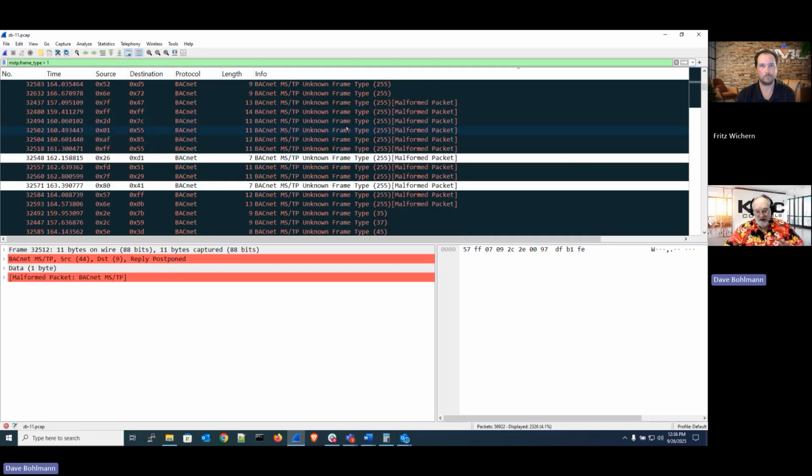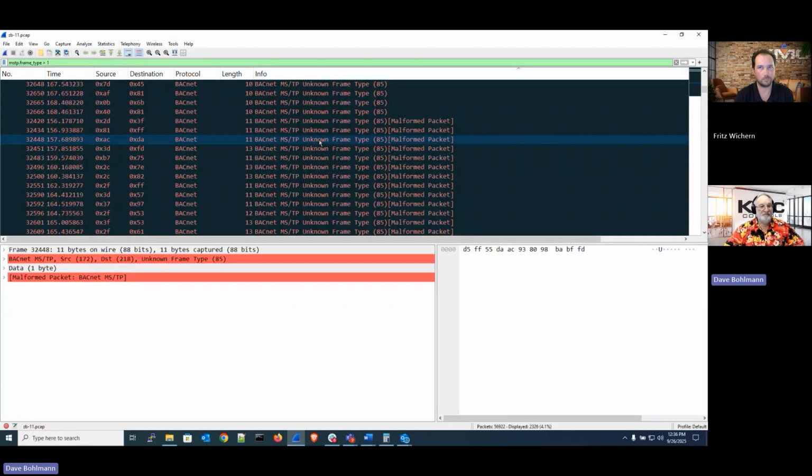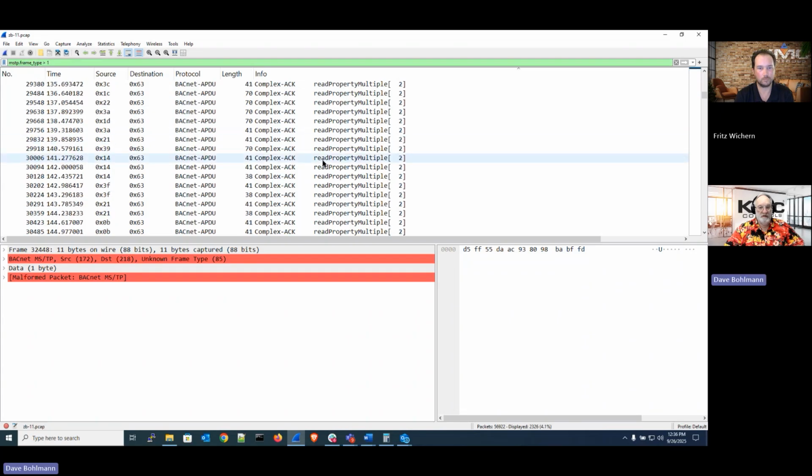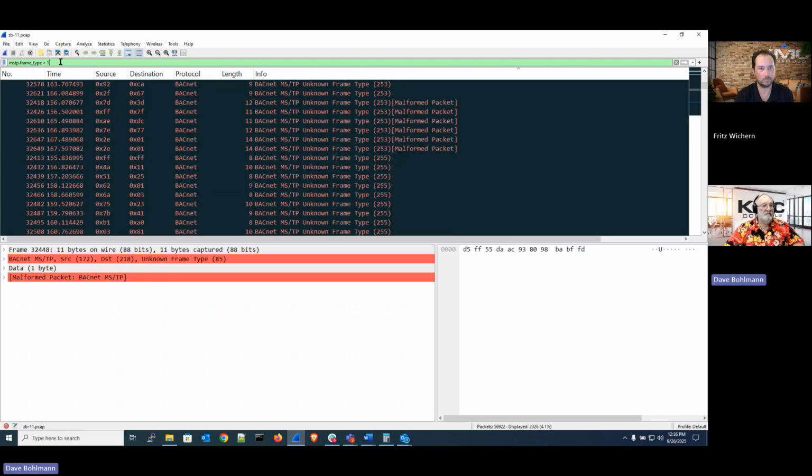But you should not see, you might see a few of these once in a while, but not nearly this many. And so what again was the complaint? Cannot read points. Well, if your messages are not working because there's noise on the line, that's what you're going to see. So let's see. All right, even though we have errors, let's check and see how many. Maybe it's not that there's noise on the line.